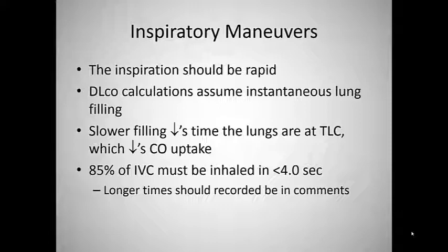The inspiration that you take when you get down to RV should be a rapid inspiration. You don't sit there and dawdle, do it over like 10 seconds. Again, I've seen this problematic in some of the ones I've watched in the text. They just kind of say, okay, take a breath in now. No, it doesn't count. It's got to be pretty quick, because remember, diffusion calculations assume an instantaneous lung filling. So the faster you get there, the better it is.